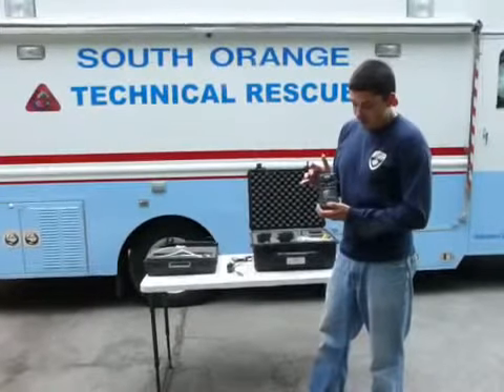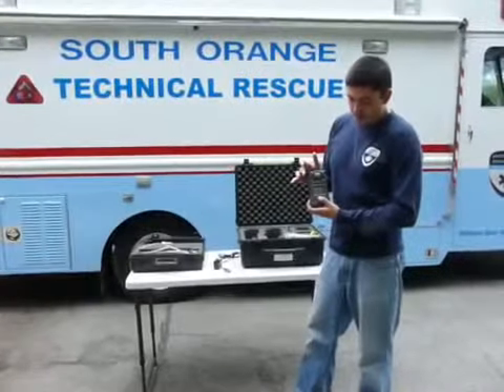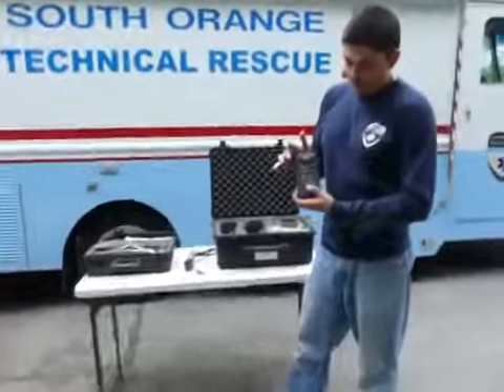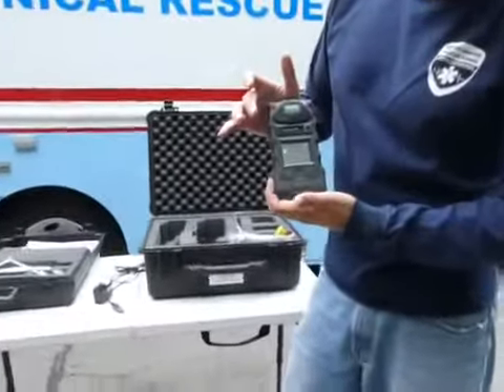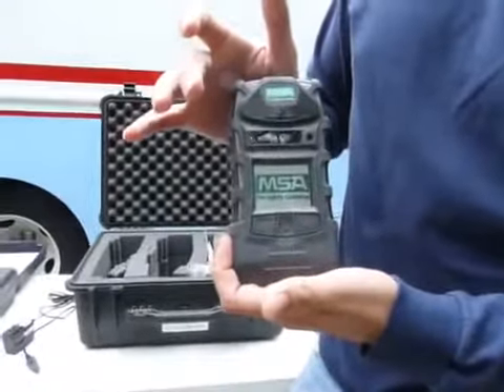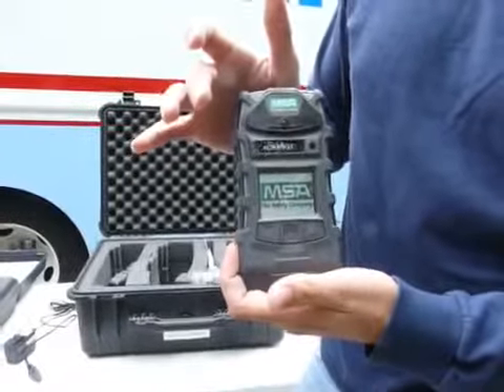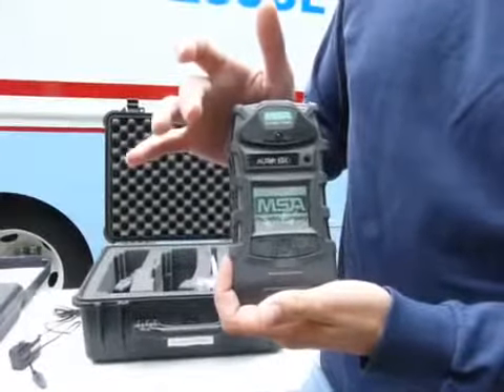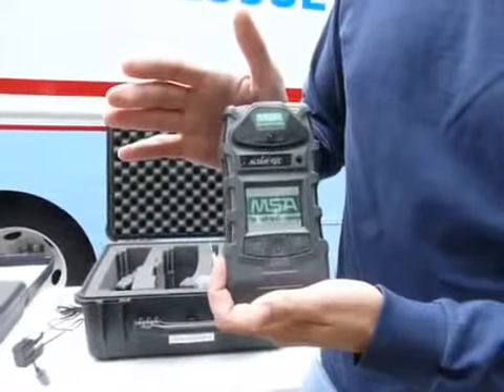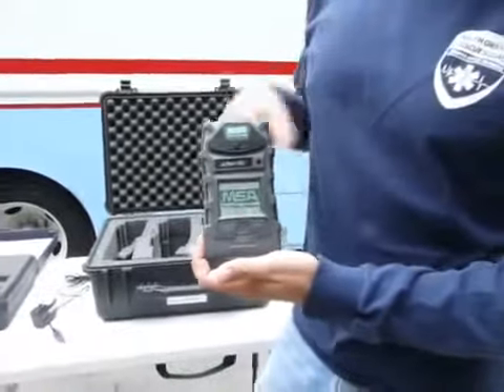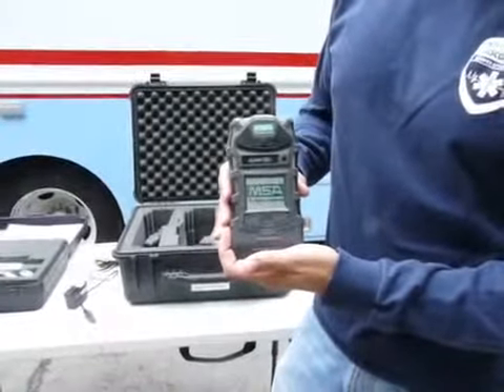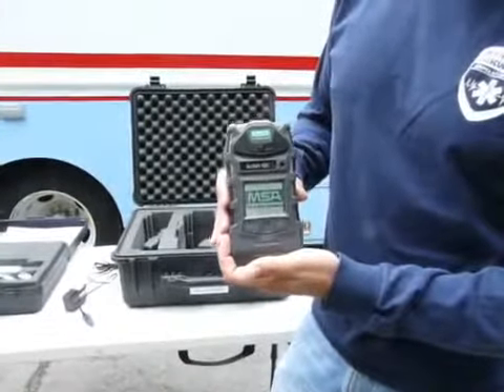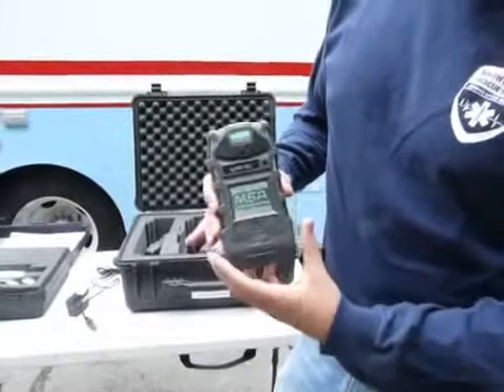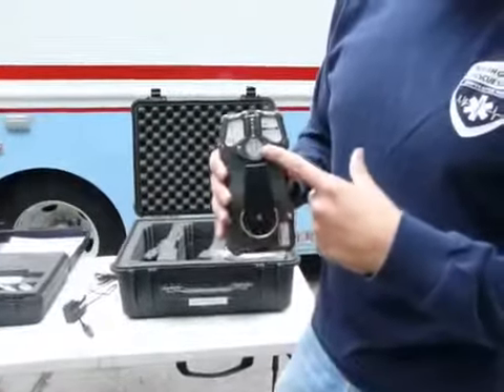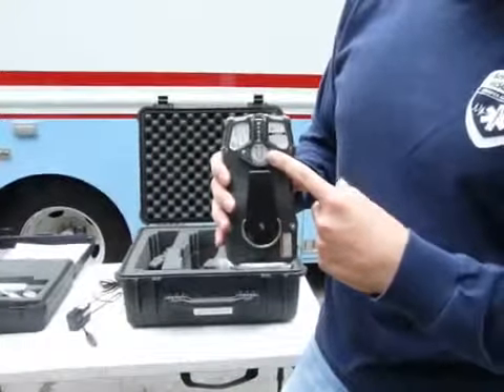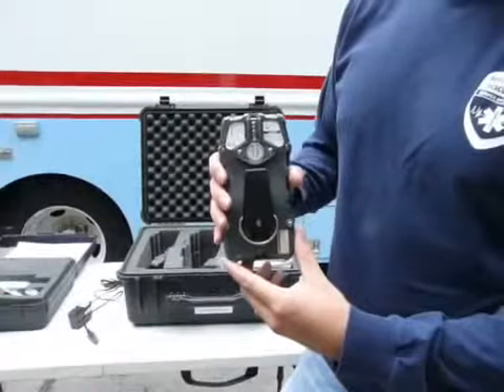To turn the unit on, this middle button right here, you hold that down. It'll immediately alarm when it first turns on, and it's going to go through a startup process where it does a variety of things. It's a computer, and like any computer, it takes a little bit of time to set up. You can hear that the internal pump just turned on. The internal pump is on the back side of the unit right here, and this pump actually pulls a sample of air in for it to check.